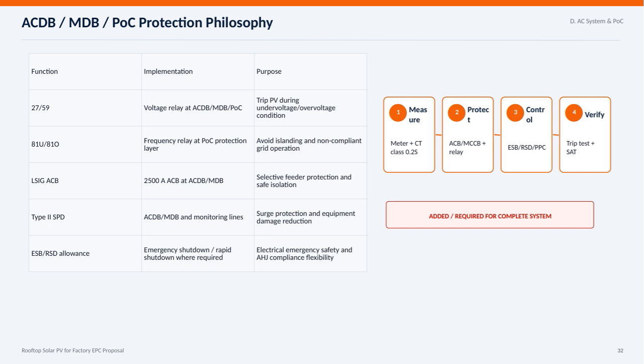The protection approach follows a clear sequence. First, we measure using high-accuracy meters and current transformers. Then protect with ACBs or MCCBs combined with relays. Control via emergency and rapid shutdown systems. And finally verify through trip tests and site acceptance testing. This layered strategy ensures a complete and reliable protection system for safe solar integration.